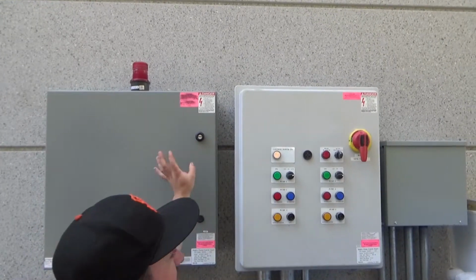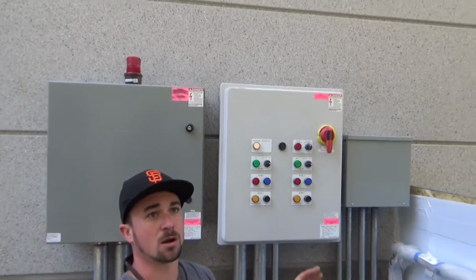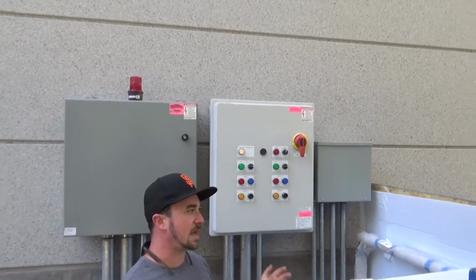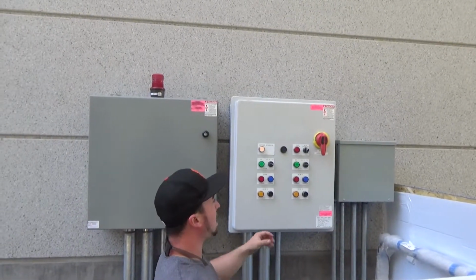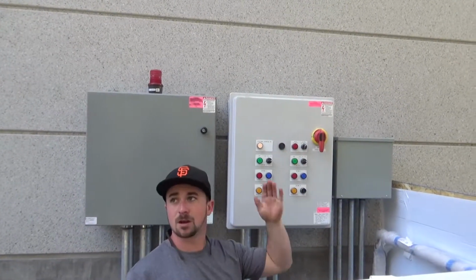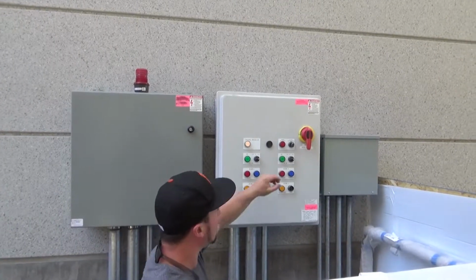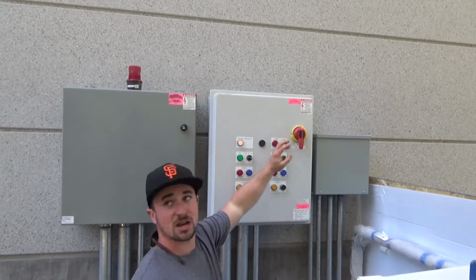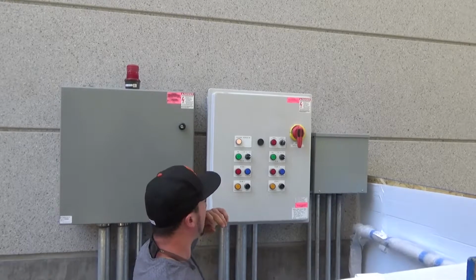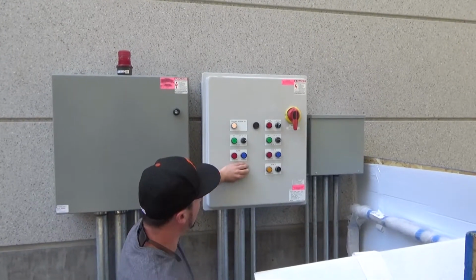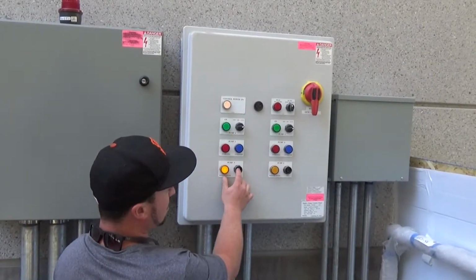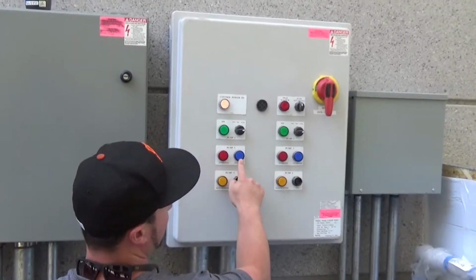So if one of these hits that float, something's wrong. Maybe both pumps failed, I highly doubt it, but something's happening if you're hitting that high water. That pit's filling up way too much. But again, that's going to be the noise you guys are going to hear if that high water trips. Say you come here and you see that lit up, or this lit up, or that one, or this one.